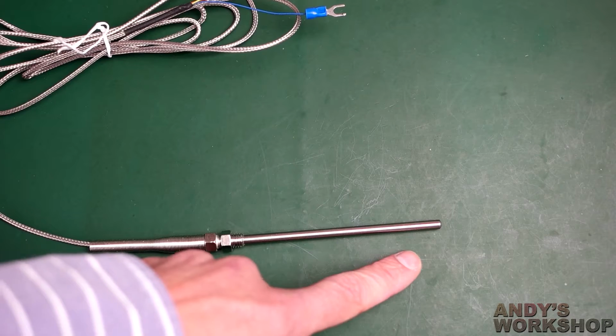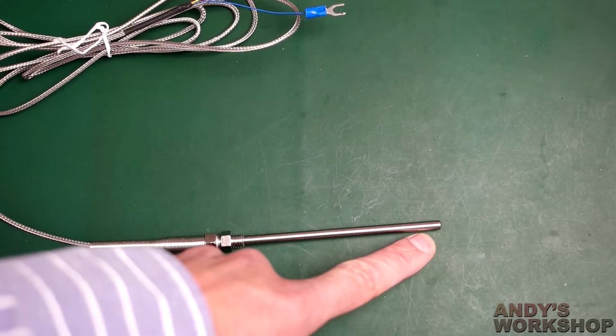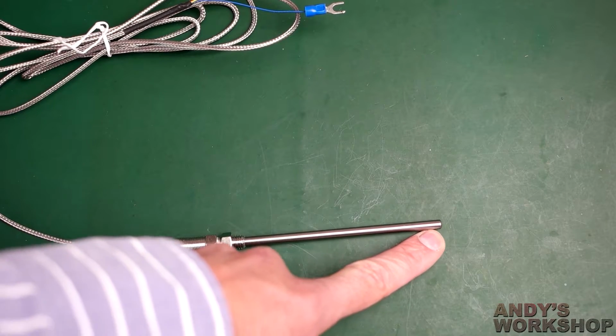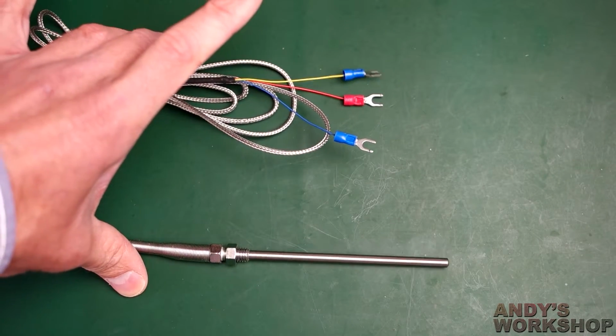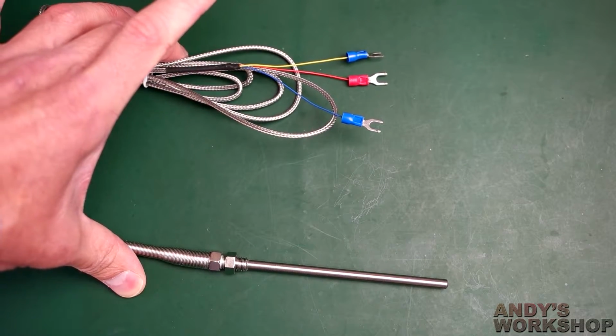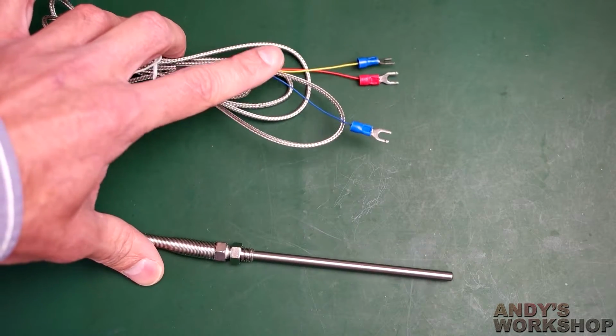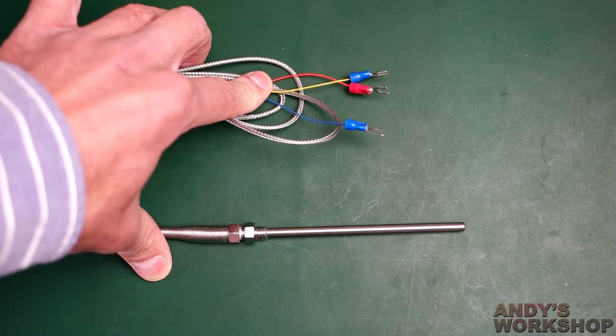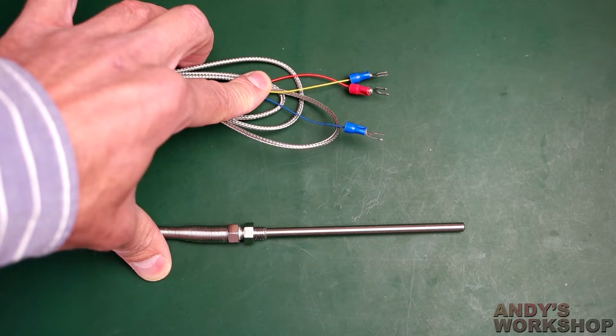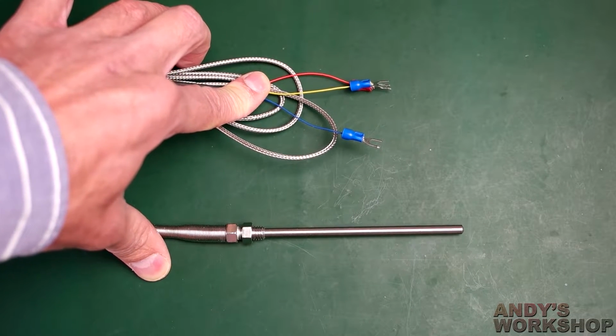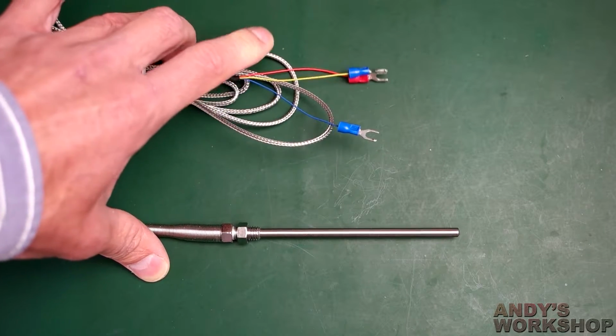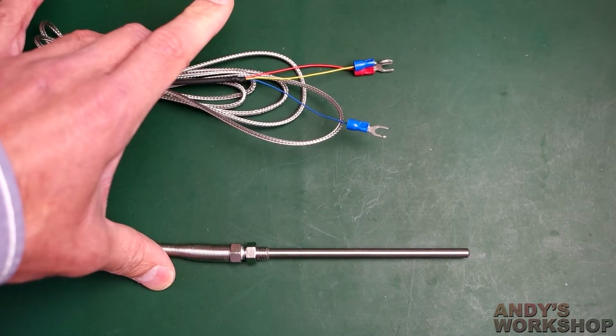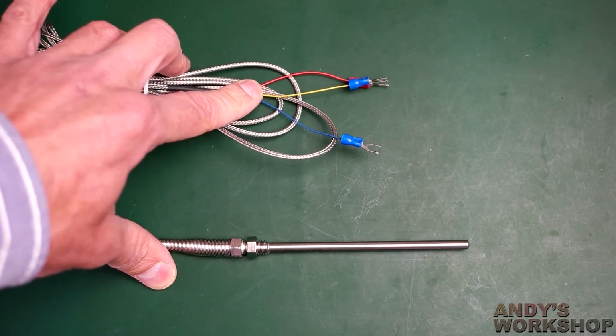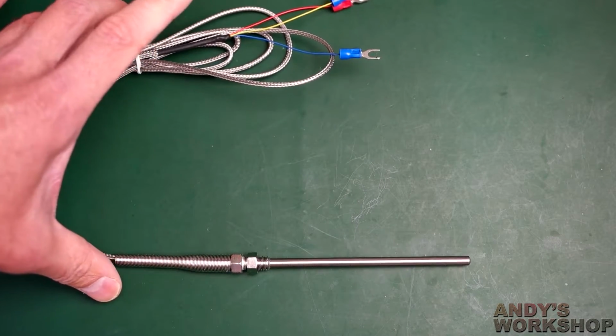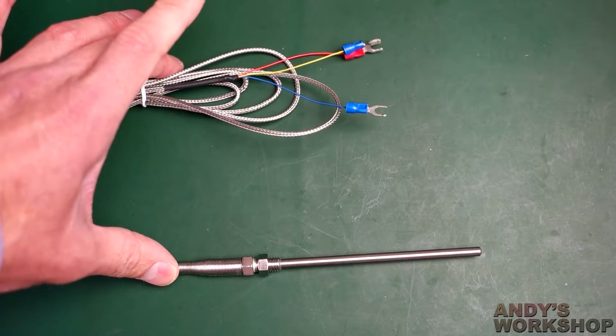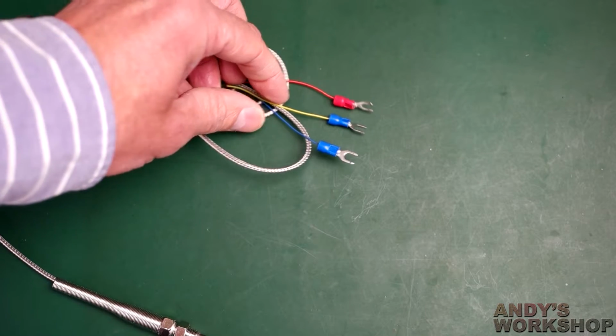I have no idea whether the resistance element in the end actually is platinum, because platinum, I would imagine, is not the cheapest material to source, and if it can be faked, it will be faked. So I don't know whether this one's real or not. But an RTD, if it is real, is the most accurate, and it's certainly the most repeatable, accurate and stable over the temperature range of all the sensors you can get. The disadvantage to RTDs is the price. A good RTD probe and a good conversion, a good sensor, is not cheap indeed, but they are the best in the class.